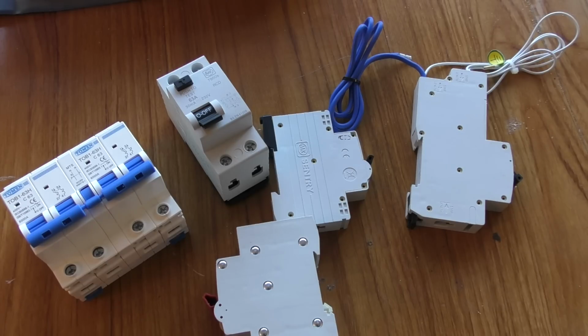Adding that switch inside the consumer unit is a slightly controversial subject, and I think it's getting into the weeds of administration and paperwork rather than actual safety. It's argued that inside a consumer unit, you're only allowed to put things manufactured by the same manufacturer as that consumer unit. I believe the regulation says that everything must be installed according to manufacturer's instructions, and some, but definitely not all, manufacturer instructions say that you can only put things in the consumer unit which were manufactured and approved by the manufacturer. I have read a few, and I did find at least one that didn't say that. I can't remember now what that was and whether it's a current or an old one.